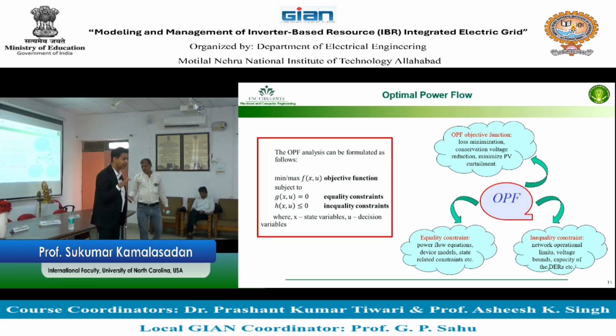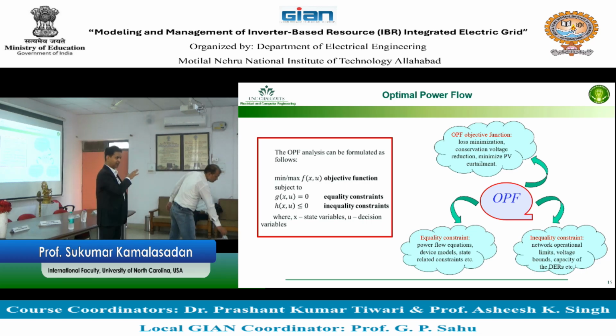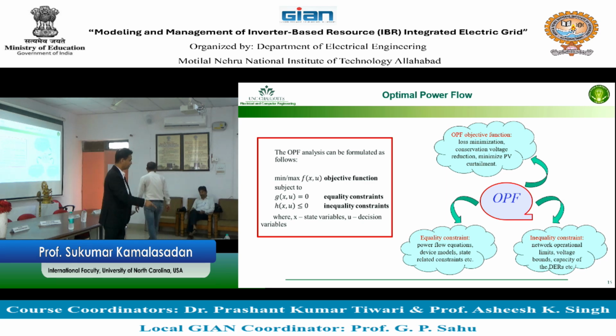Normal operating condition. PV is doing a good job. PV is not doing anything bad. It's coming to you. But we know that if that comes to the electric grid, it's messed up. What will you do now? You cut. Will you cut it to zero? No, you may not cut it to zero. You may cut it to a level where the voltage is balanced.